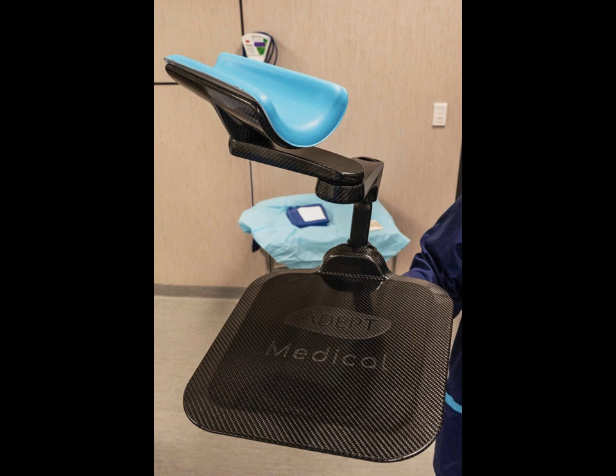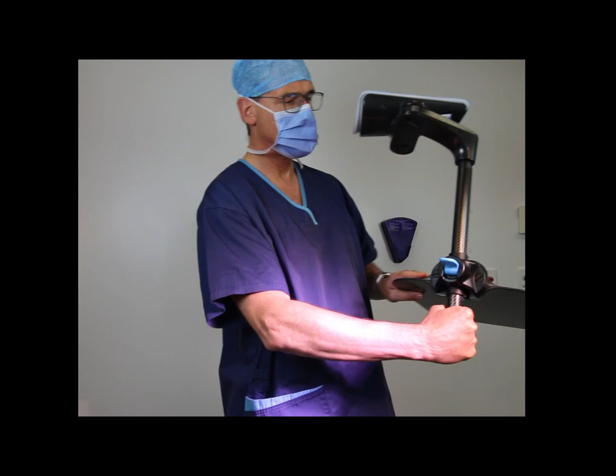Accordingly, I designed the arm support with the help of engineers from Adept Medical, an Auckland-based medical engineering company. The device has a padded armrest which supports the forearm. It is articulated with 3 joints that enable it to move freely in the horizontal plane. The tension on these 3 joints can be adjusted. It has a shaft and a baseboard which slips under the head cushion on the operating table. The quick-release locking device allows the height of the arm board to be adjusted and locked, and the shaft can be rotated relative to the baseboard.